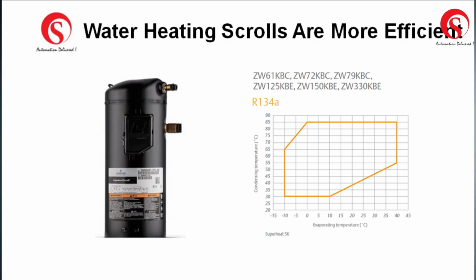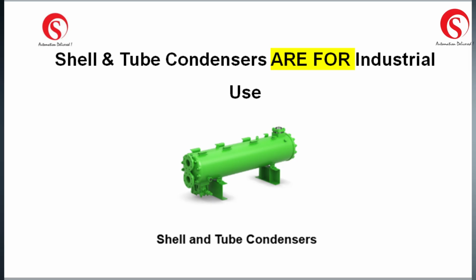The refrigeration system consists of an air cooled evaporator, a finned coil with fans to circulate the air. Second, there will be a water heating scroll compressor, which is more efficient than reciprocating and other types of compressors. There will be a shell and tube heat exchanger condenser, which is generating the hot water. People may be using or might have seen different types of heat exchangers for the condenser, but usually an industrial application should be long lasting, at least serving for 10 years, 15 years, 20 years.